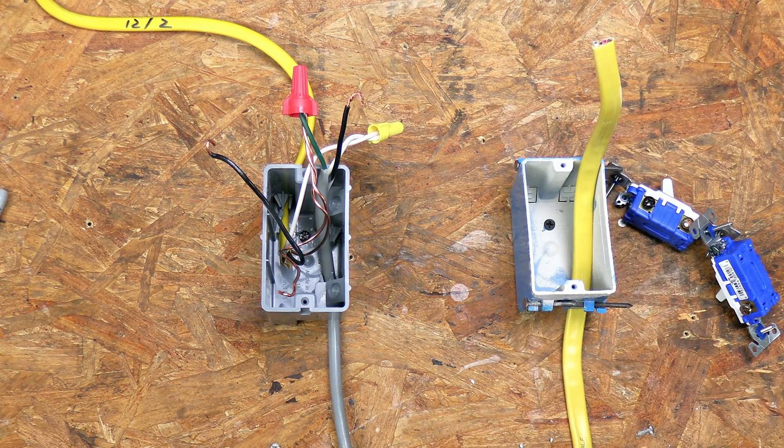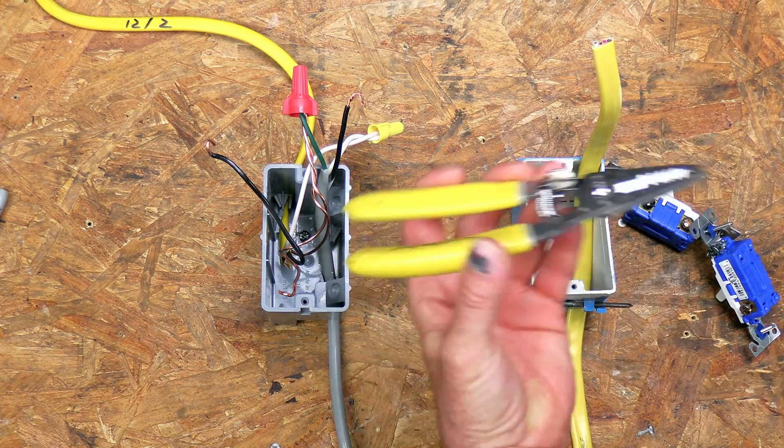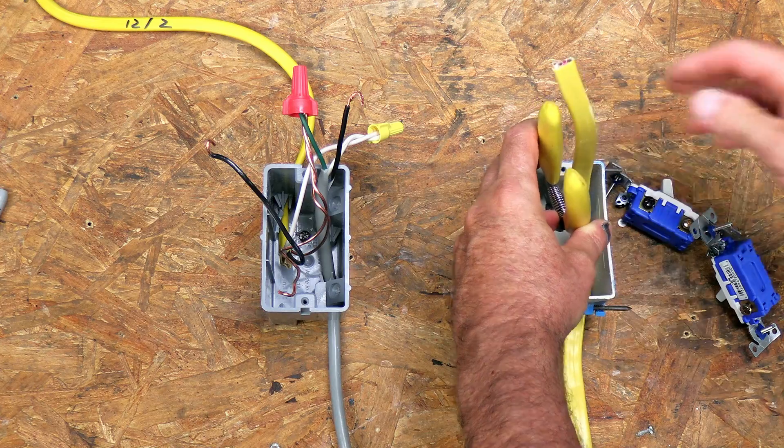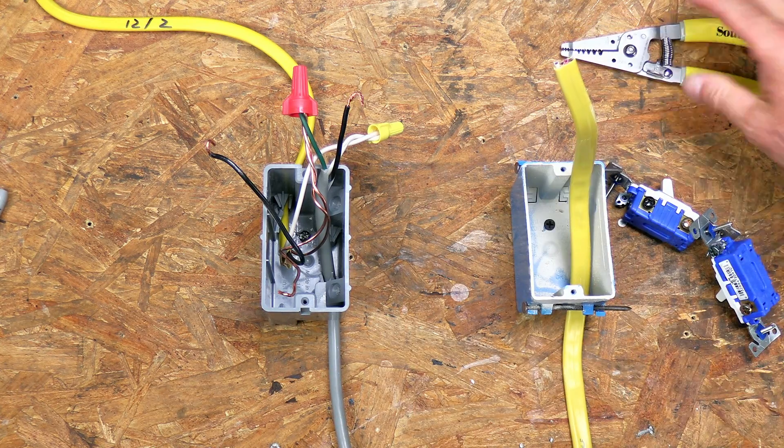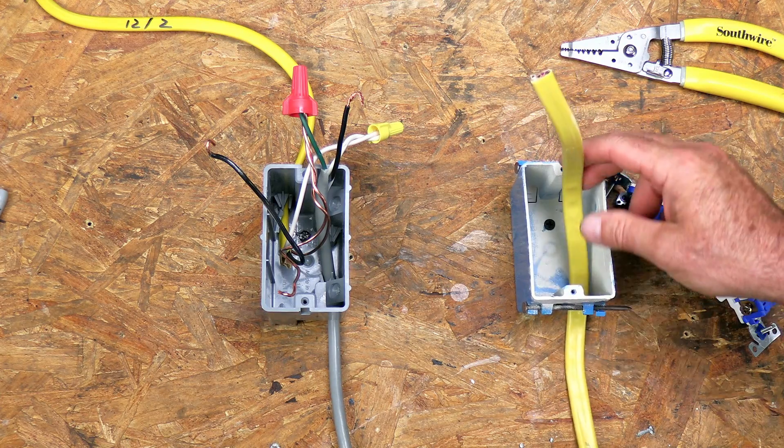Now I usually like to leave about 8 inches from the back of the box. My pliers are approximately 8 inches long, so I will run it approximately the length of the pliers. I think the code is 6 inches from the back of the box, but I actually like just a little bit extra wire right there.